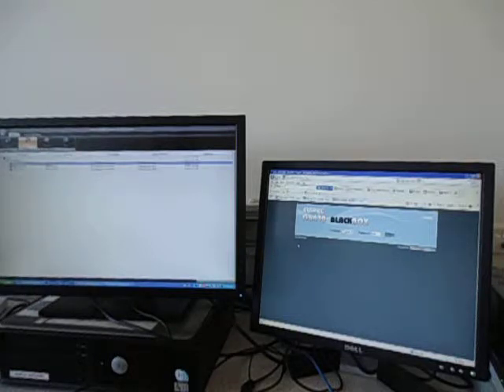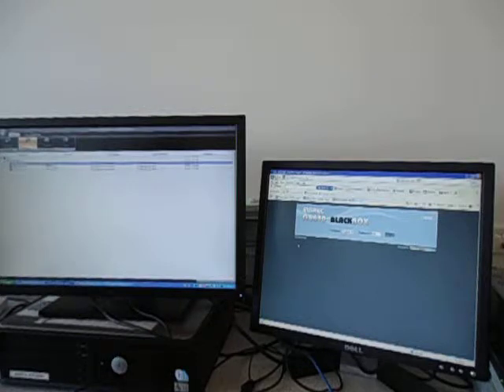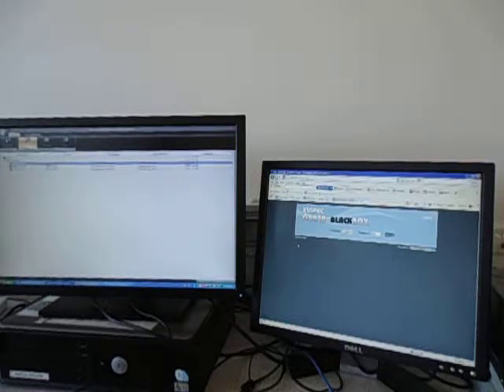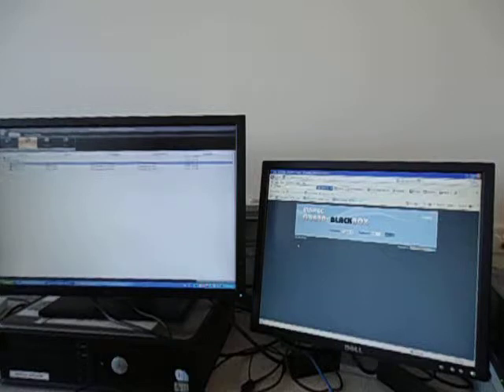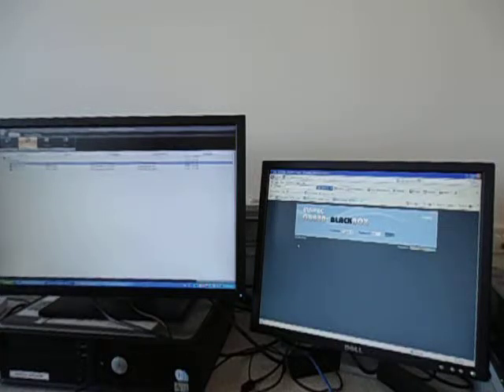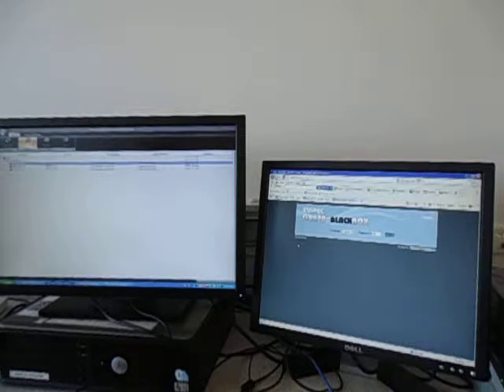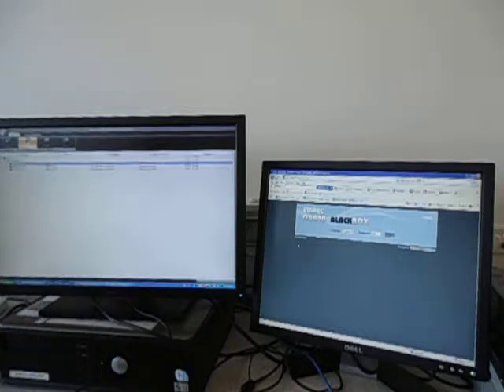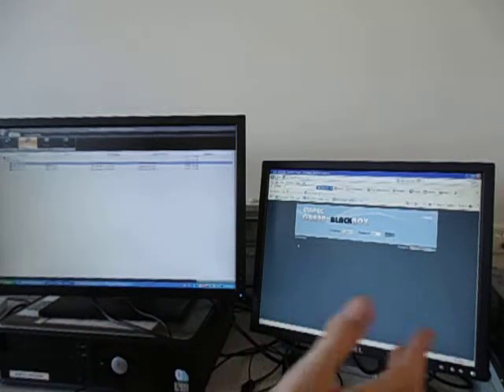Yesterday I was trying to set up PQ SCADA along with Microsoft SQL database and investigator on a couple of other computers. All these computers were imaged by ITD and there was something preventing it from success. I think it might have been a firewall setting which is for security and it was just preventing communications between the EnSpec black boxes and the software.